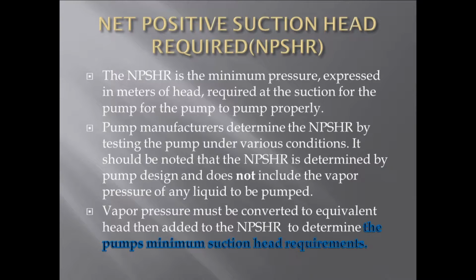Vapor pressure must be converted to equivalent head, then added to the net positive suction head required to determine the pump's minimum suction head requirements.